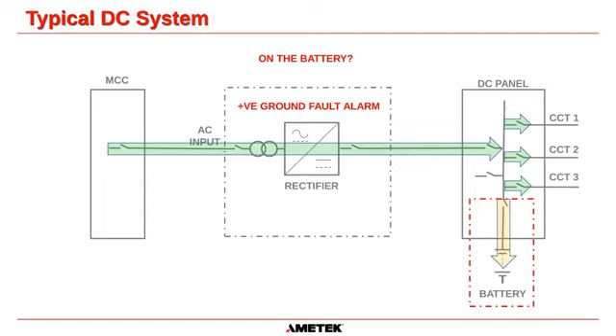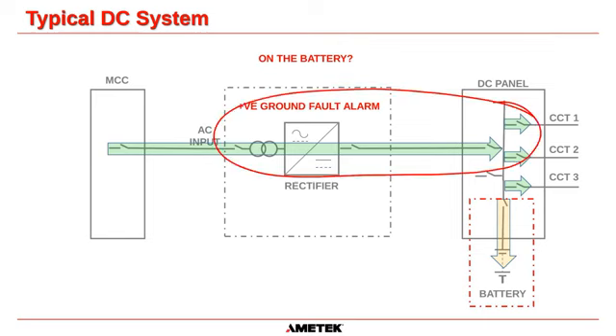Okay, you cannot open a battery breaker on a DC system that doesn't have any capacitors in the charger, because the actual output of the charger will look like that. It will be pulsating DC, and if some of your loads are sensitive to these dropouts in between when it goes down to 0 volts, then you could cause an issue. So make sure that your rectifier charger does have capacitors inside it before you open the battery breaker. Okay, but what you can do with all of these breakers closed, everything on, if you open the battery breaker and the DC ground fault alarm clears on your charger, then there is a ground fault on your battery somewhere.